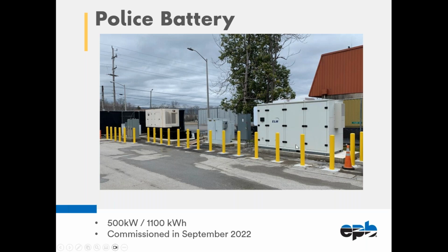This is the battery on the far right, and this is the generator that was installed at the site. The battery is 500 kW and is able to support the site for probably about 4 or 5 hours. Their peak load is a little over 200 kW, but they don't get that high that often, so we can run the site off of the battery and the solar for the most part.